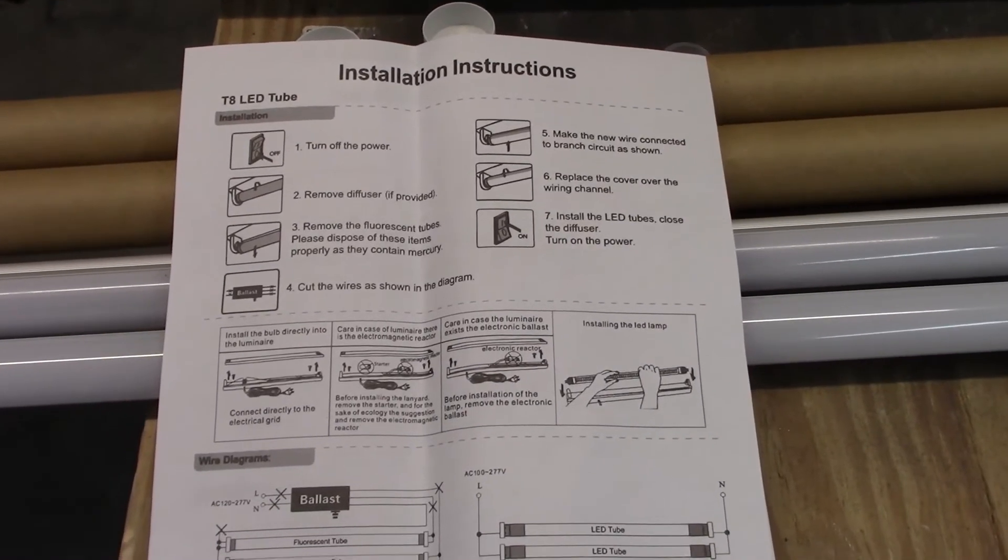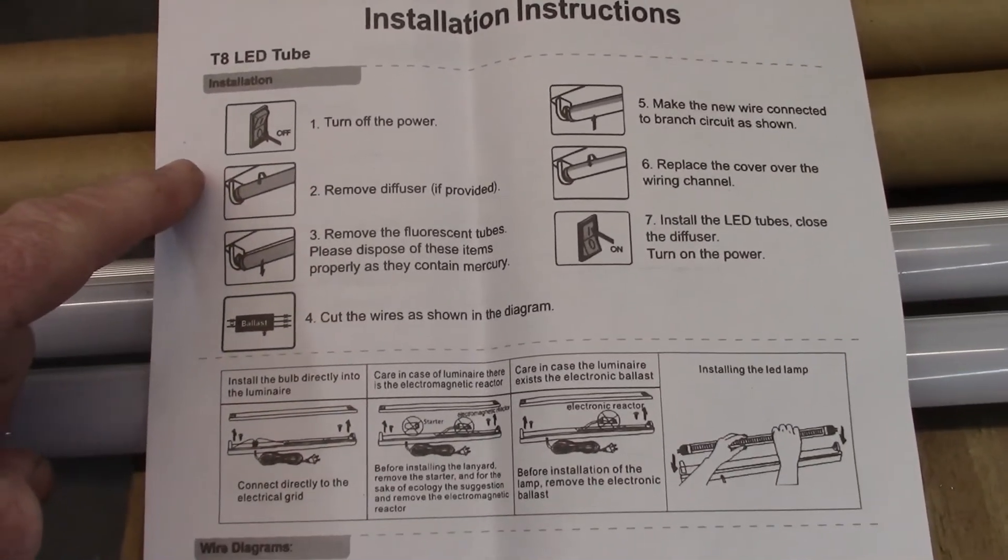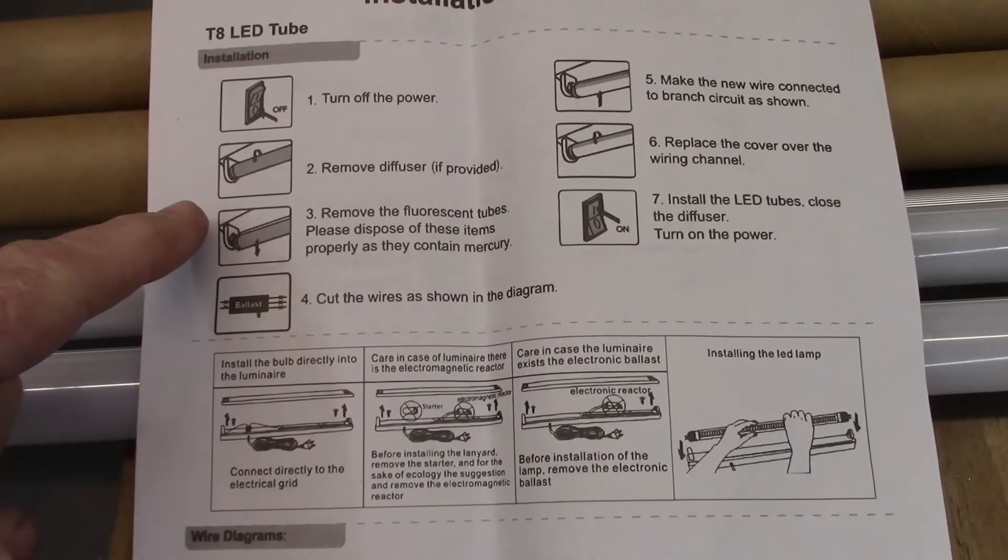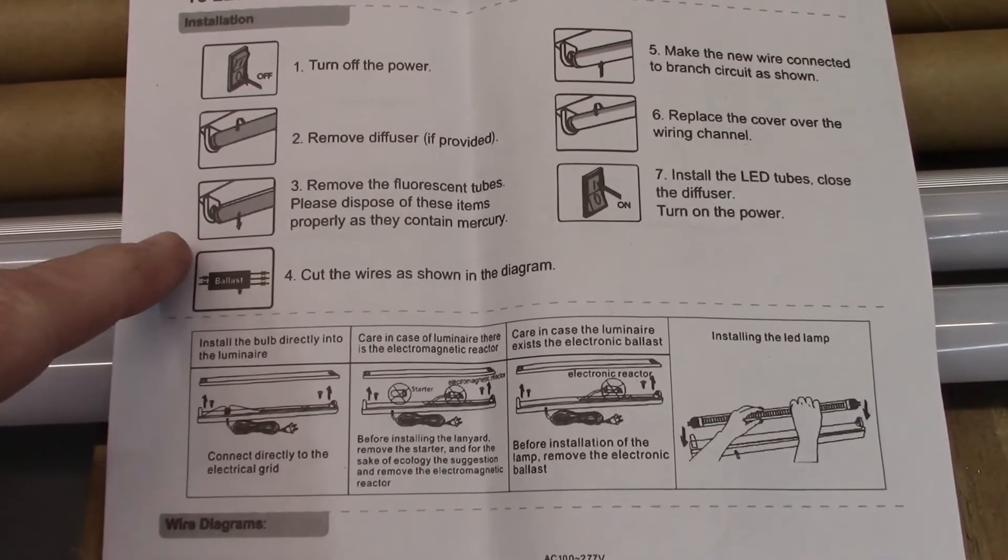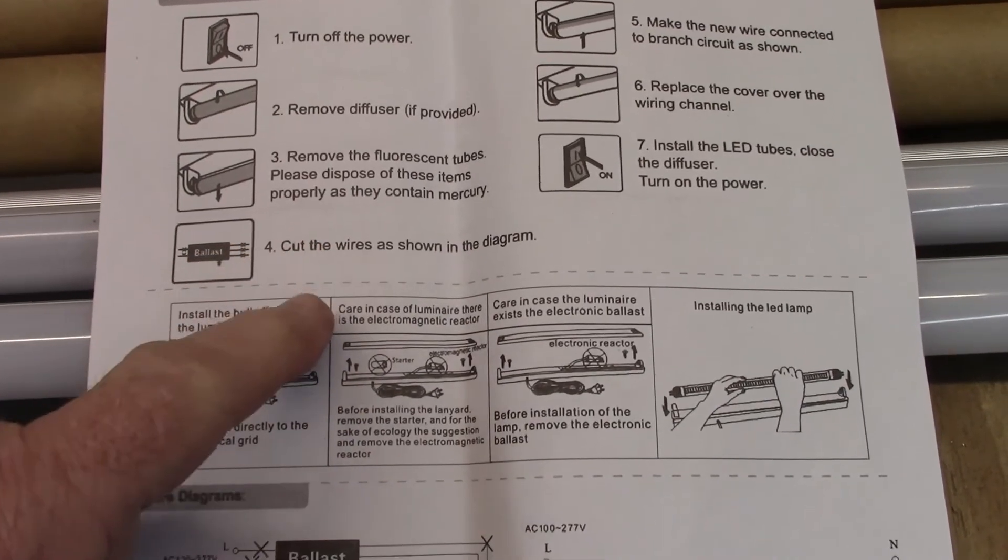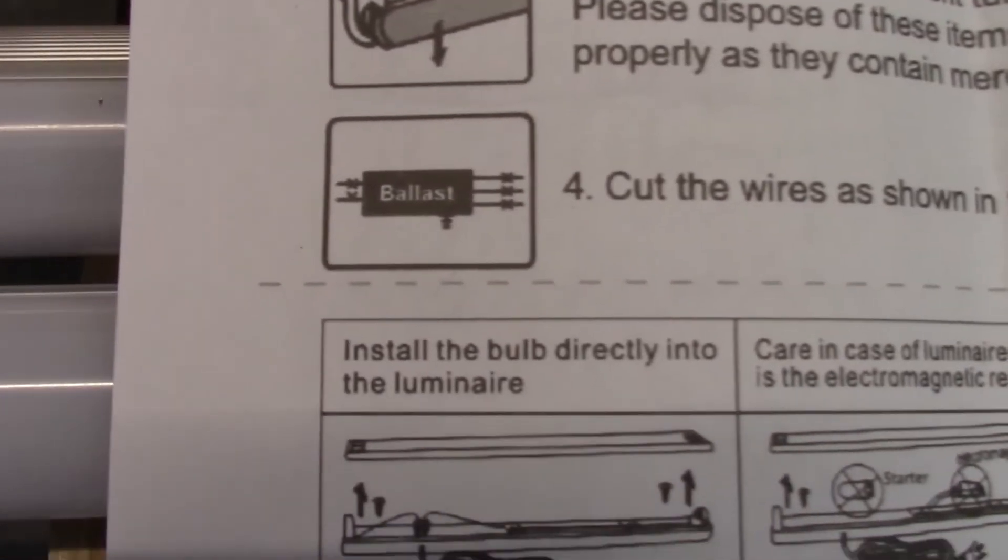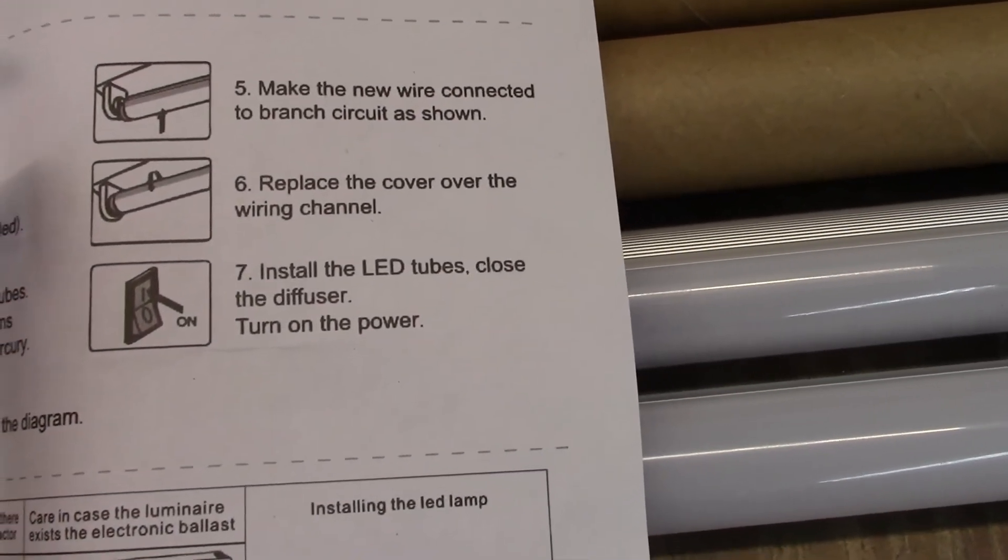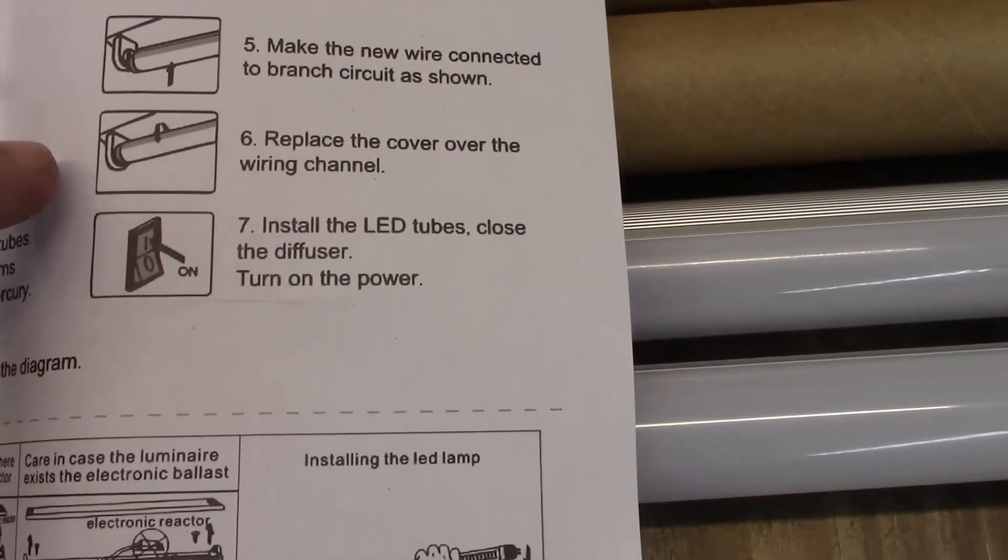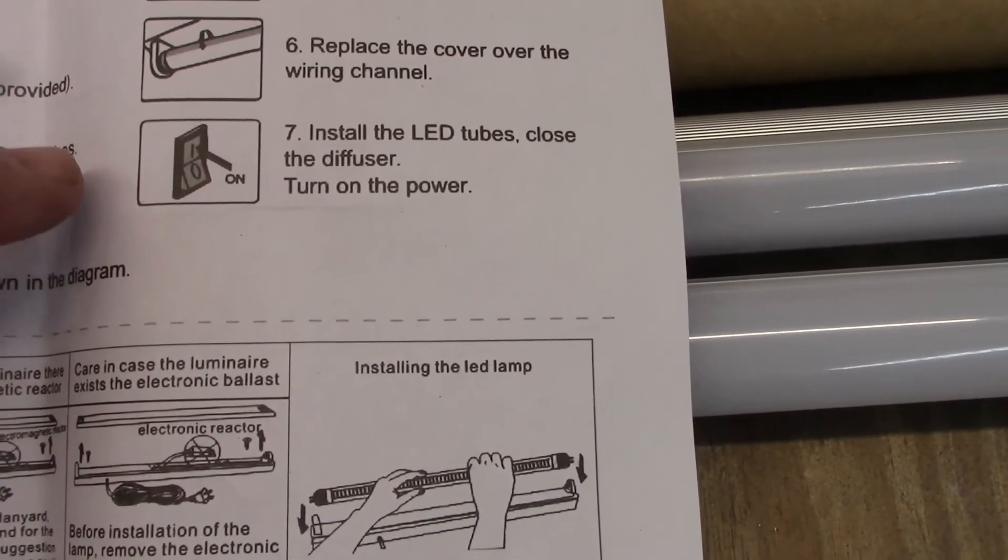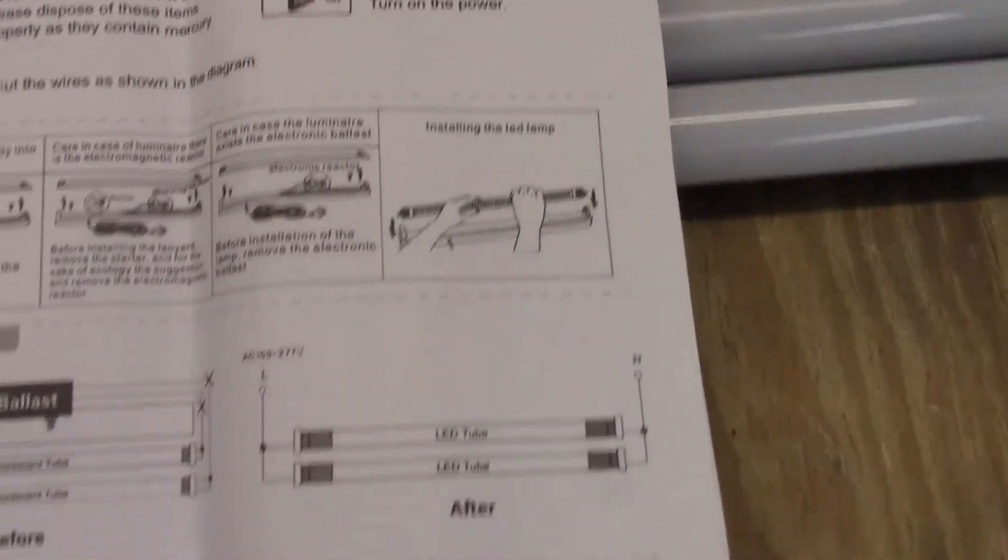So here's a look at the provided instructions. Step one, turn off the power. Two, remove diffuser if provided, which I don't have that. Three, remove the fluorescent tube. Please dispose of the items properly as they contain mercury. Four, cut the wires as shown in the diagram. Five, make sure the new wire connected to branch circuit as shown. Replace the cover over the original wiring channel and install the LED tubes, close the diffuser, turn on the power.